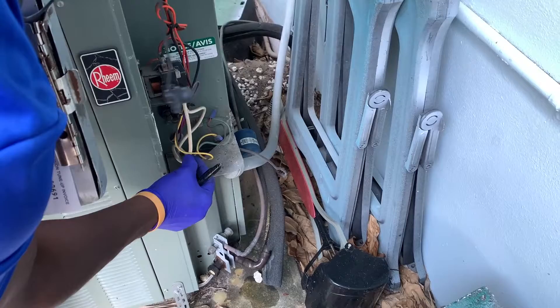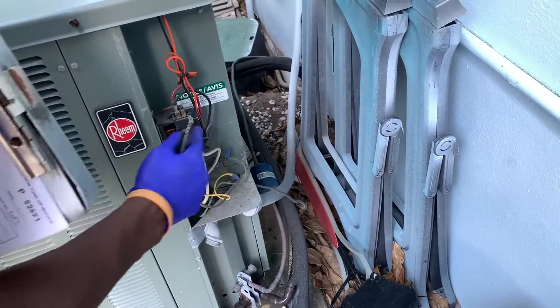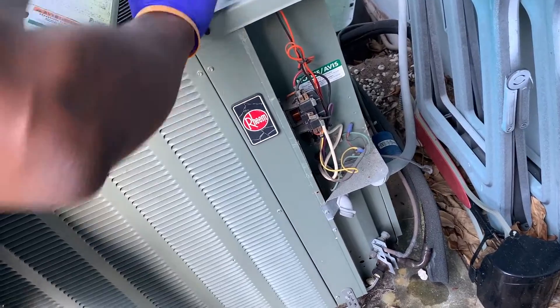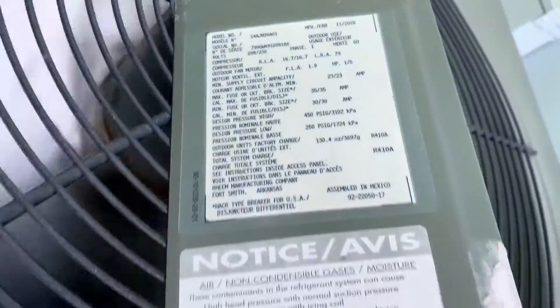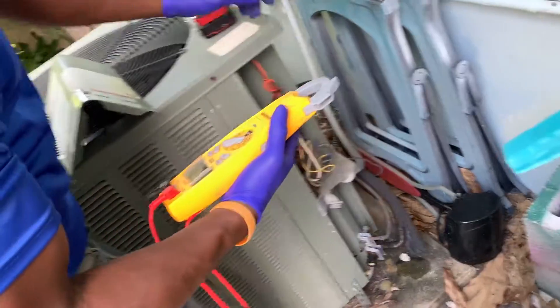It's on the ECM, so here's your fan, the fan capacitor, and the compressor. You have one dual-run capacitor which is a 45 microfarad.